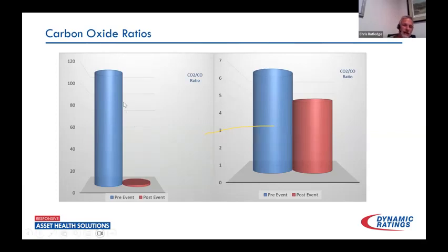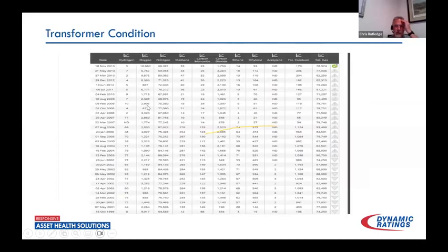However, nitrogen blanket, this is not unusual at all. And typically we will see that ratio with nitrogen blanket transformers tends to climb over time. So this was another transformer I had in service. We obviously had some problems here.